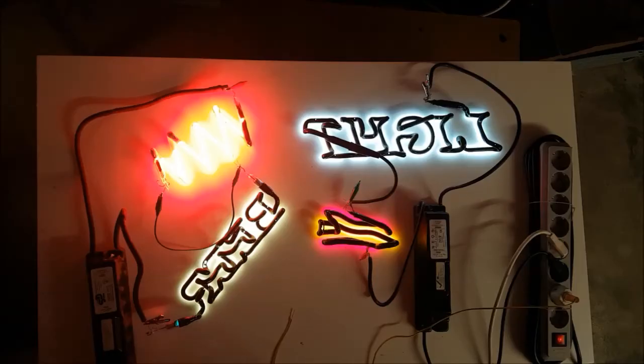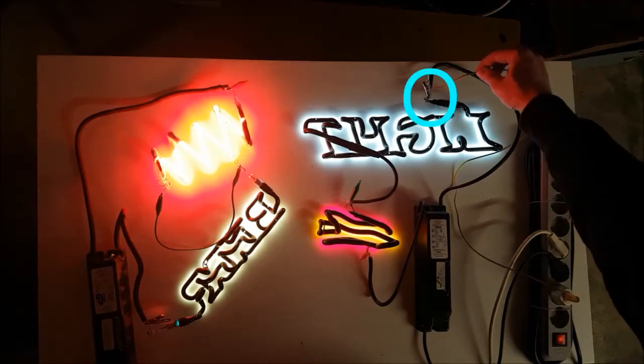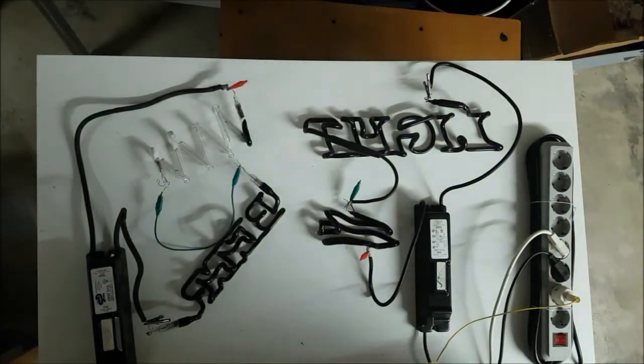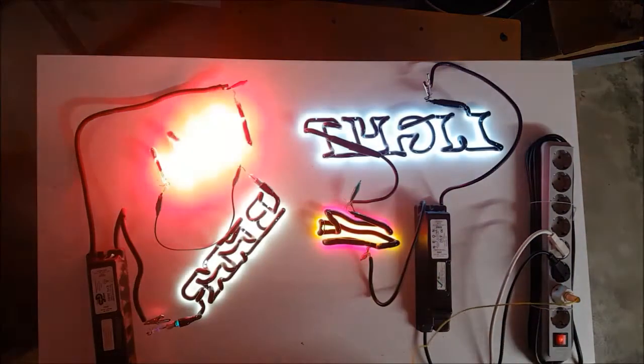The two basic safety functions these electronic transformers have is ground fault detection. I'm going to demonstrate this to you with this ground wire that I have connected to the outlet. If I put this ground fault, let's say to this electrode connection over here, the transformer will shut off and needs a moment to recover. The same on this end. Shut off.